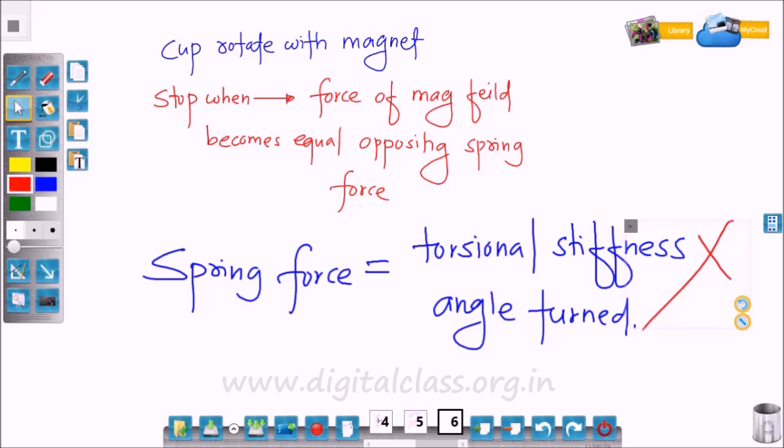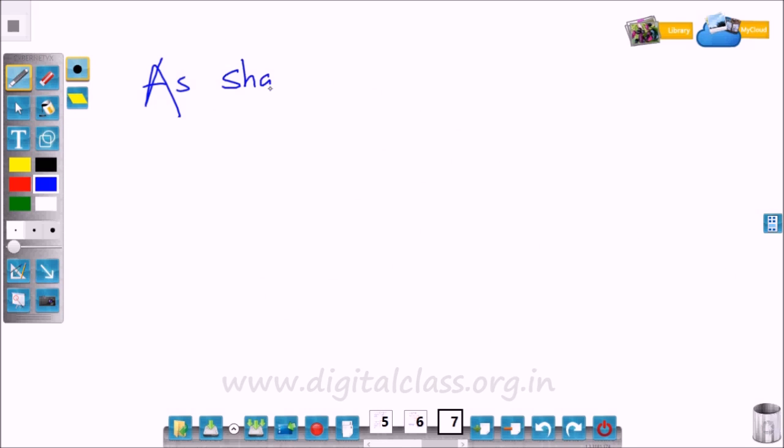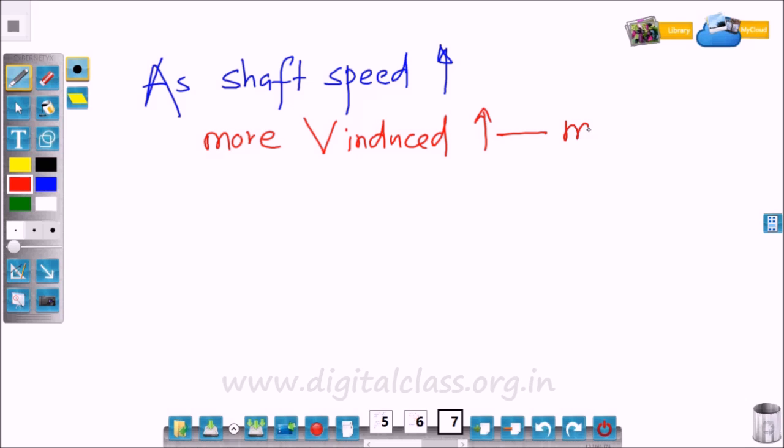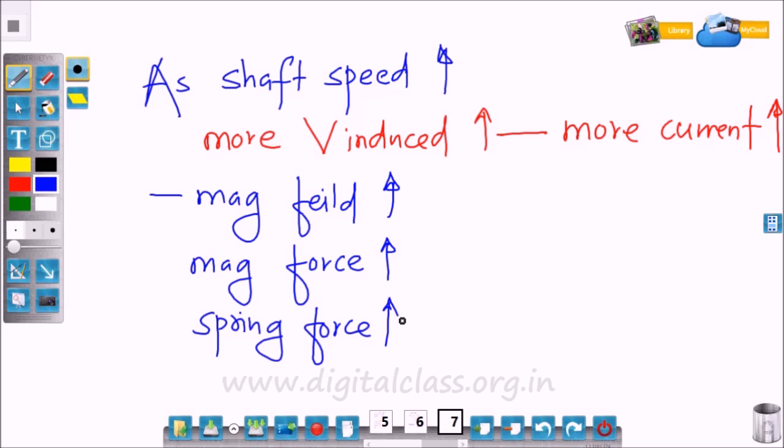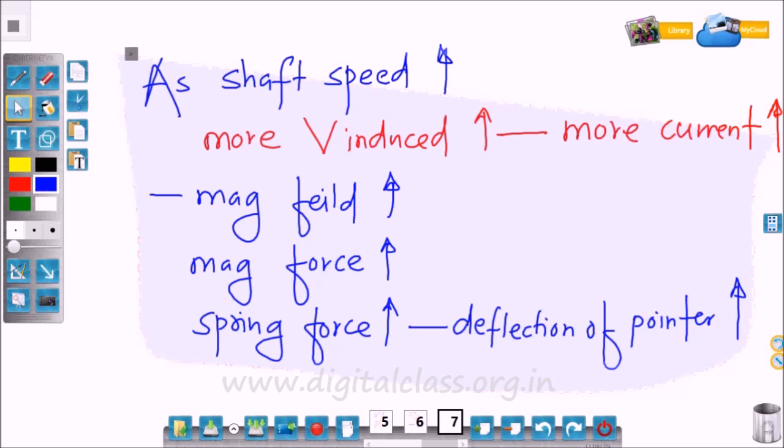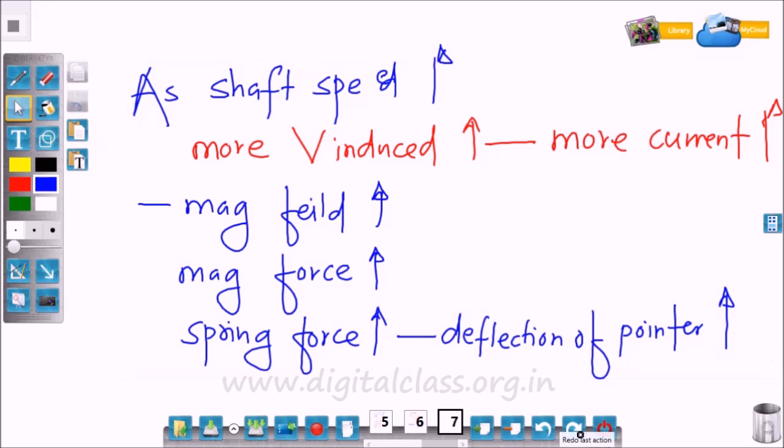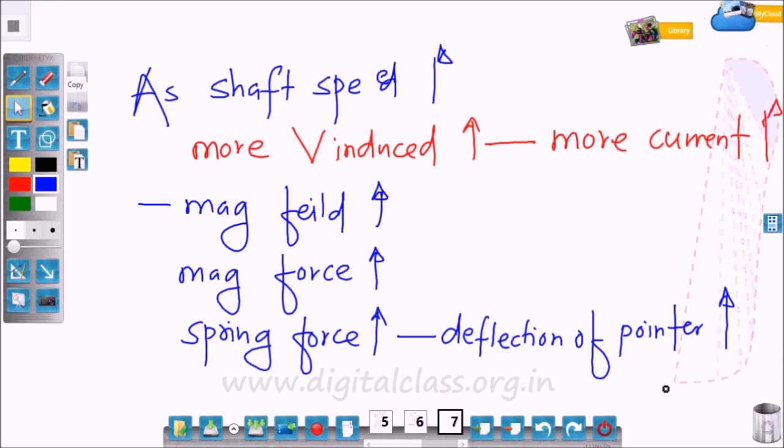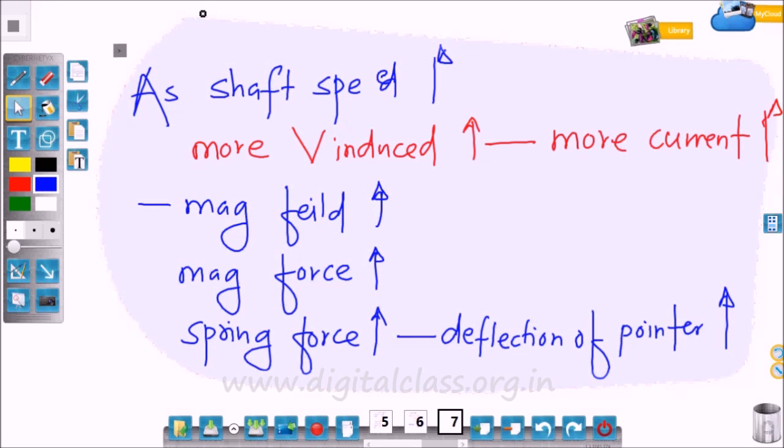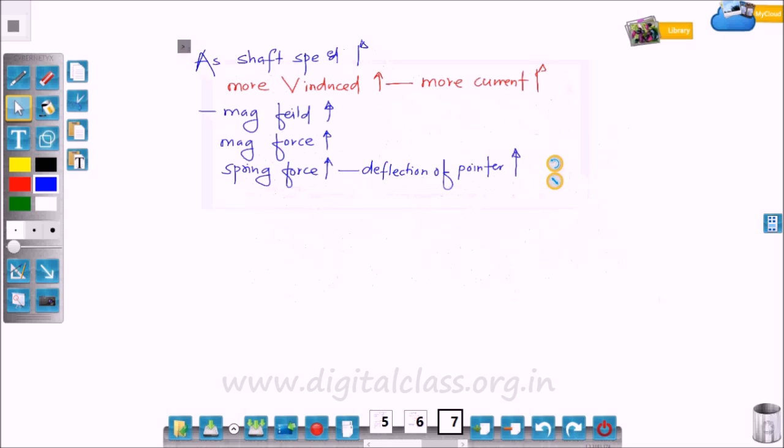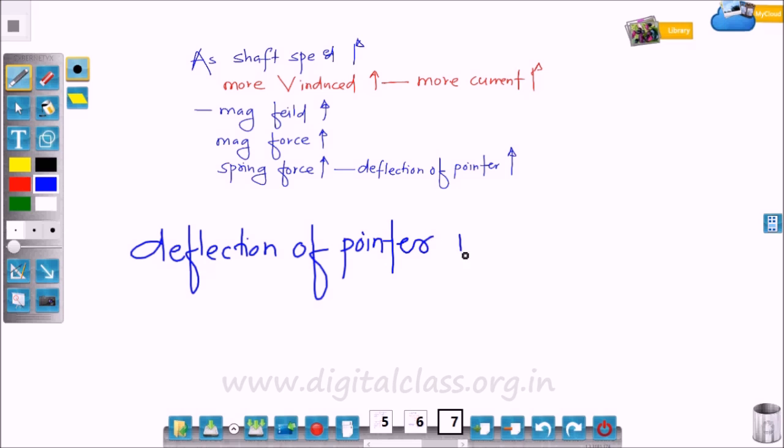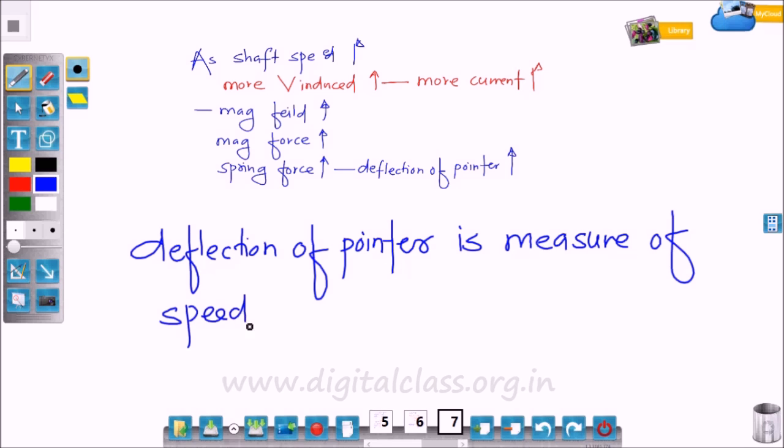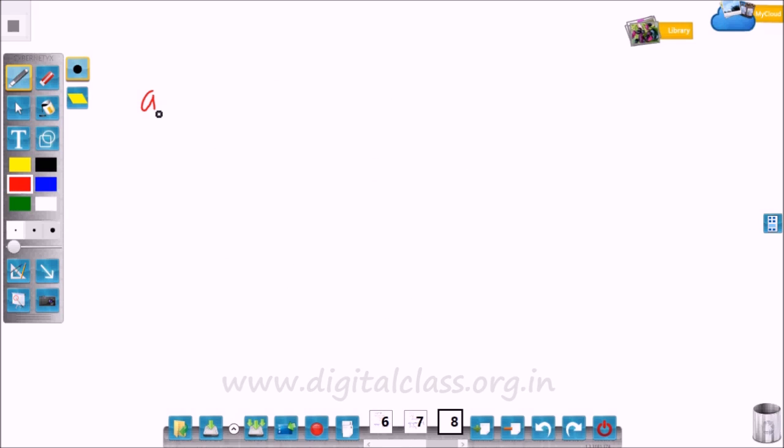As shaft speed increases, more voltage gets induced and more current flows through the drag cup. So the magnetic field also becomes stronger, and the magnetic force also increases. That's why the spring force also increases to overcome this magnetic force. Higher is the spring force, higher will be the deflection of the pointer. So here, deflection of pointer is a measure of the speed of the shaft.